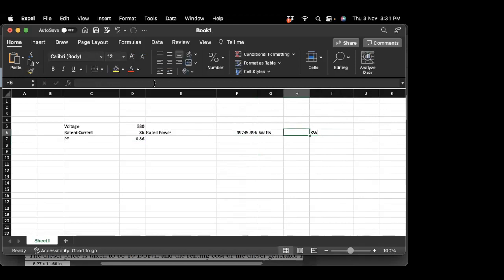By simply dividing that by thousands, it's around 49.745 kilowatts. Okay, this is the worst case scenario power, because simply this power reflects the highest possible current to be drained from our pump.